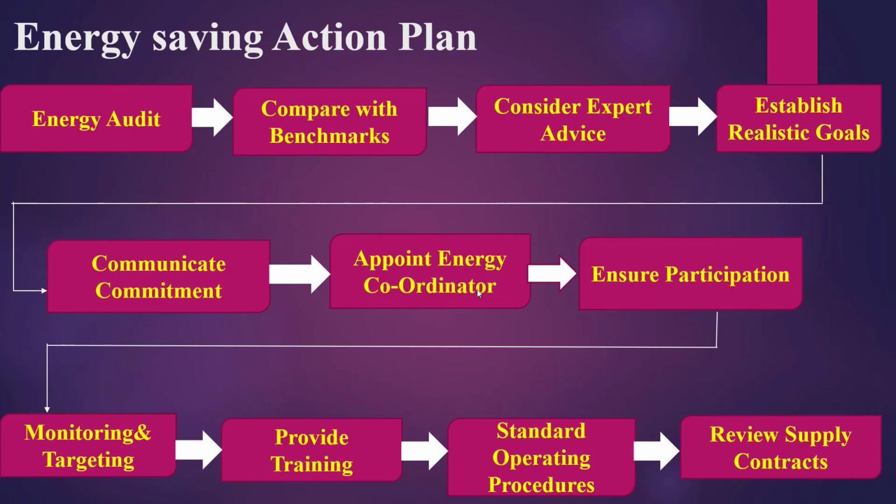Targeting. Targeting is the process of setting targets in order to provide an incentive for reducing waste. In an individual hotel, target consumption figures are generally set with reference to historical consumption levels. If the hotel has been extended, altered, refurbished or has had new facilities added, your targets will need to reflect the anticipated impact of these changes. Correction factors also need to be applied to account for any significant alterations in occupancy and weather conditions.